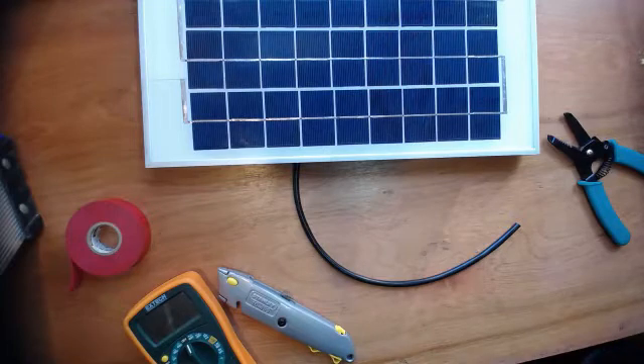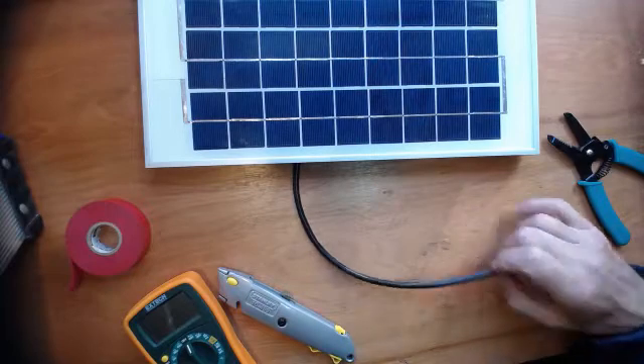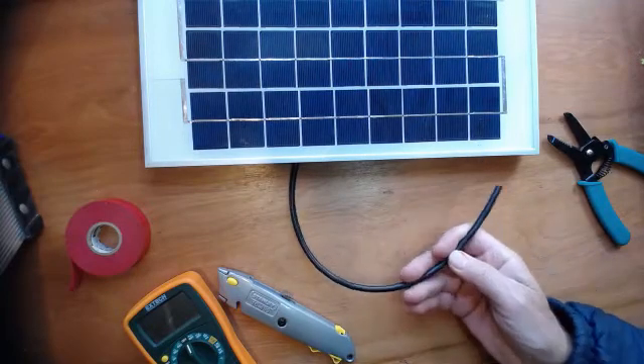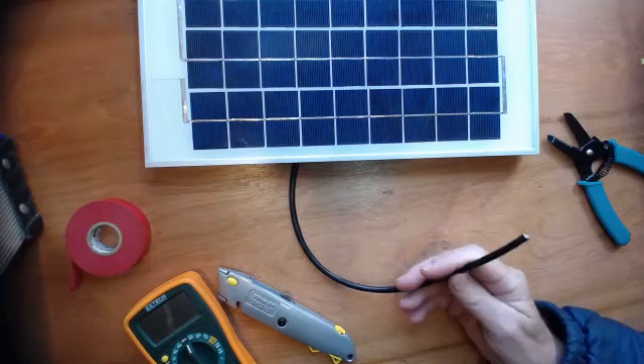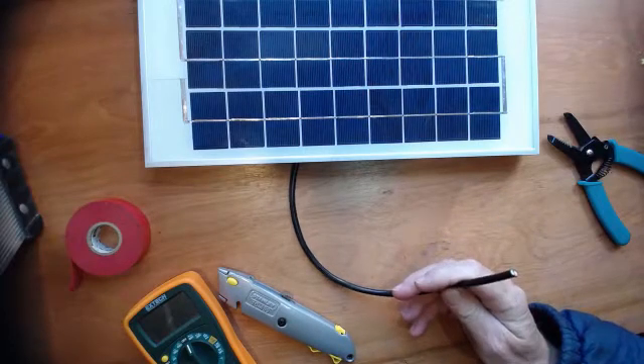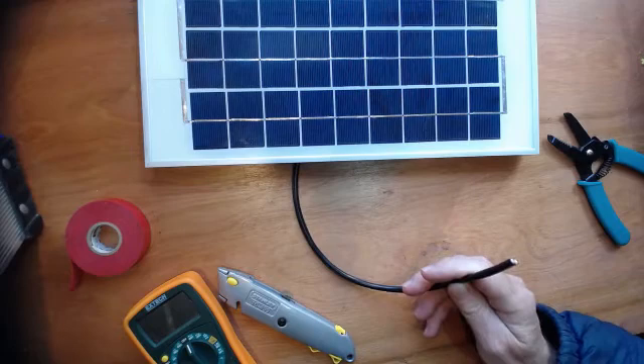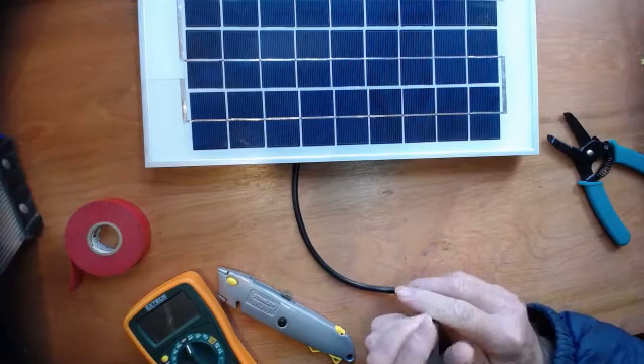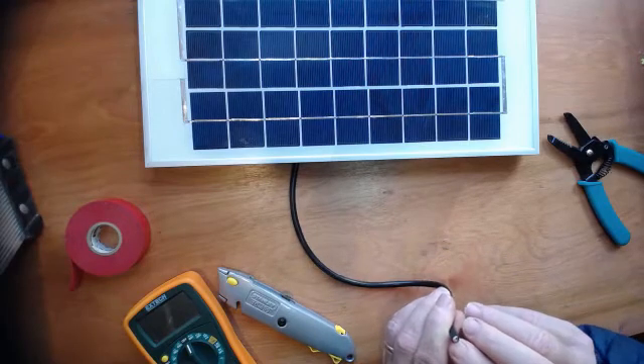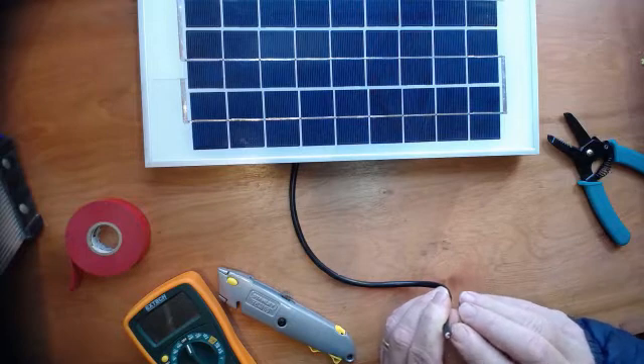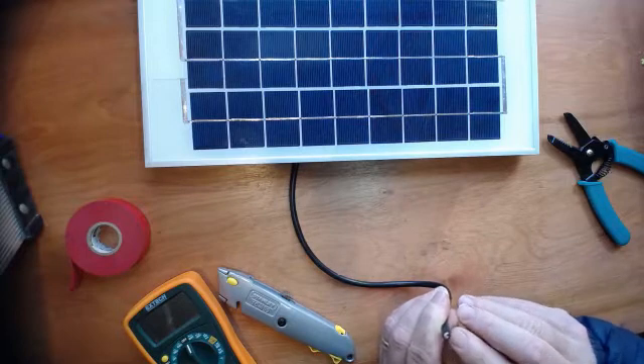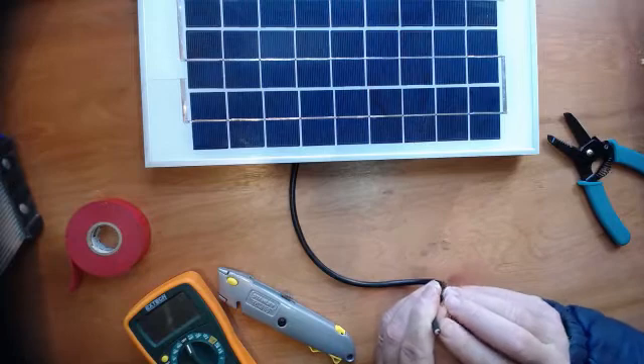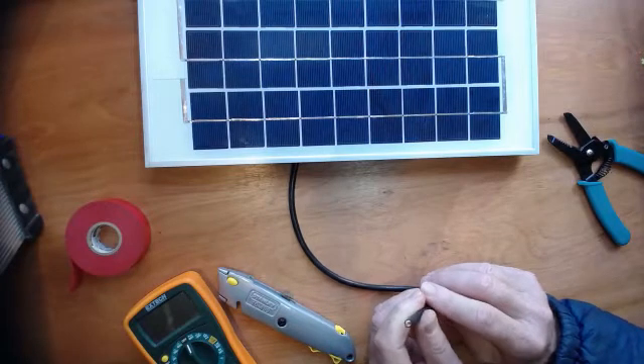We recently learned that a lot of you got solar panels that have a lead coming off of it that is not stripped and does not have bare wire ends. When you hook your solar panel to the home run cable using the WAGOS, you're going to need to have about a centimeter of bare metal from the positive lead and a centimeter of metal from the negative lead to hook up to your home run cable.